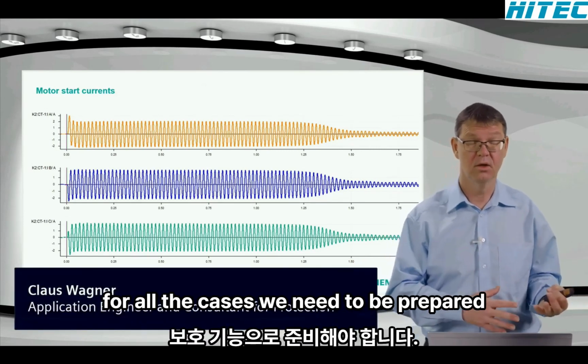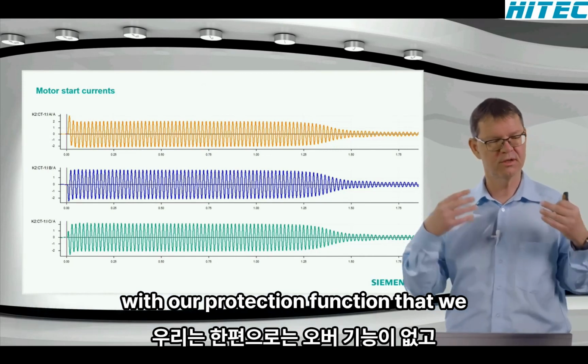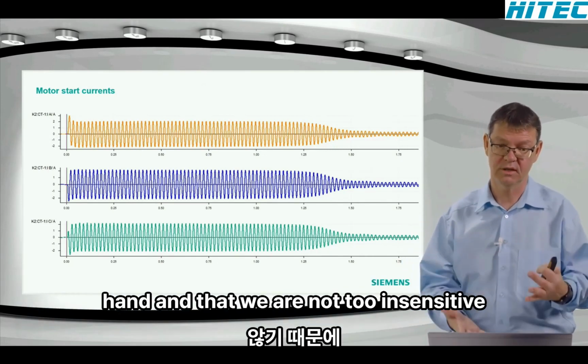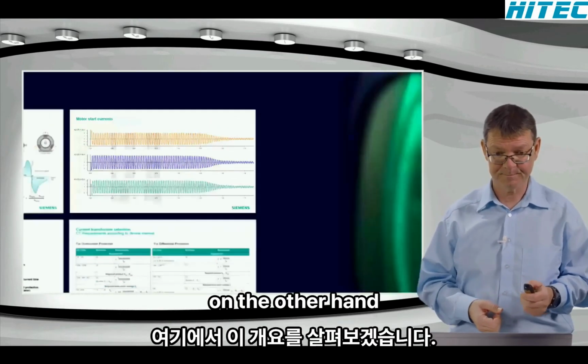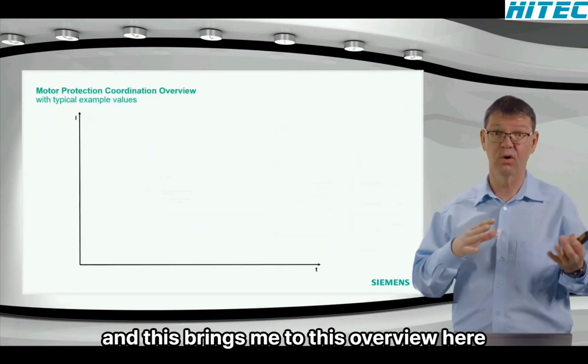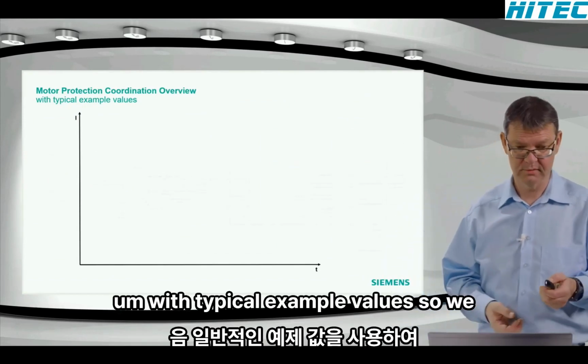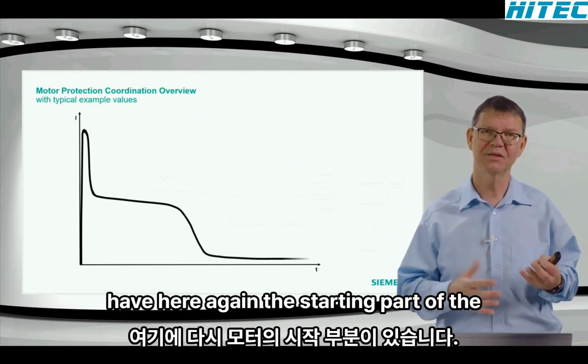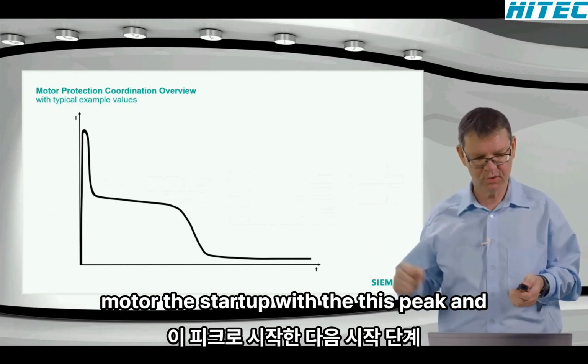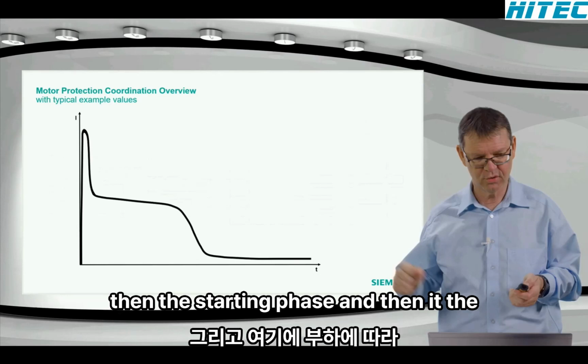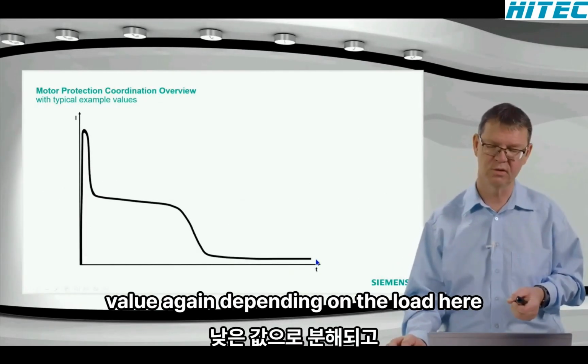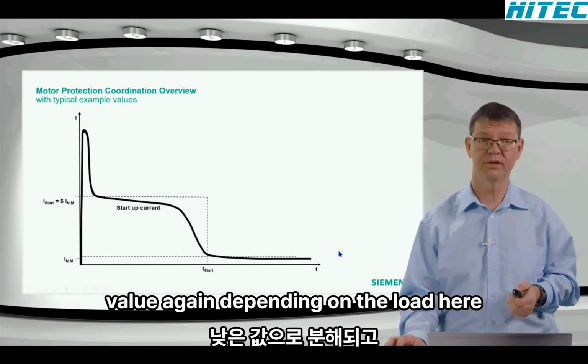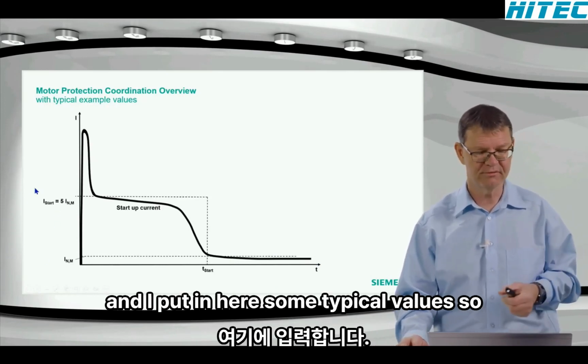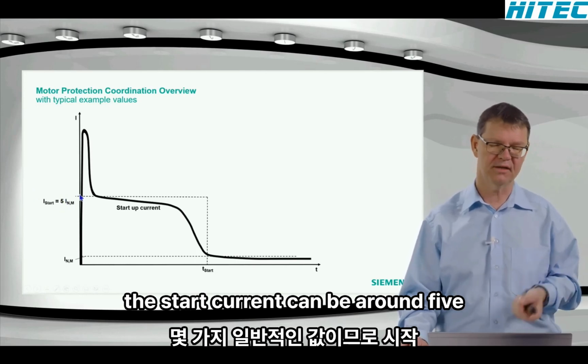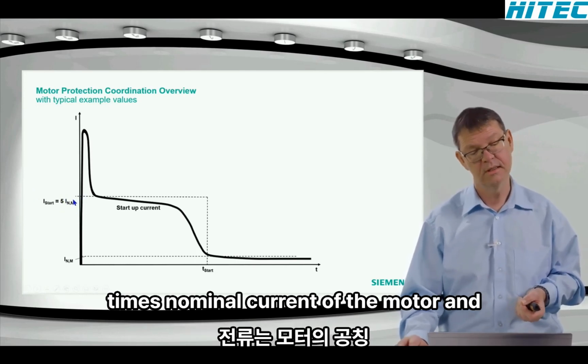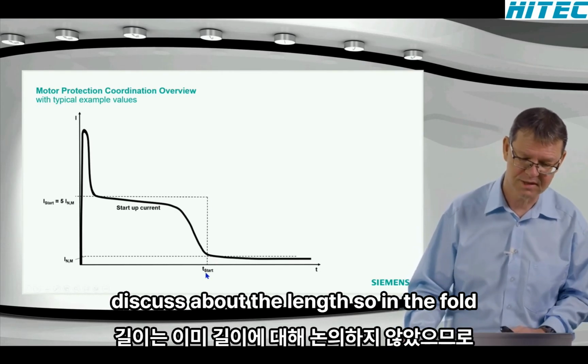And for all the cases, we need to be prepared with our protection function so that we don't have an overfunction on the one hand and that we are not too insensitive on the other hand. And this brings me to this overview here with typical example values. So we have here again the starting part of the motor, the startup with this peak and then the starting phase, and then the current drops to a relatively low value, again depending on the load. And I put in here some typical values. So the start current can be around 5 times the nominal current of the motor. And the length, as already, no, we did not discuss the length.